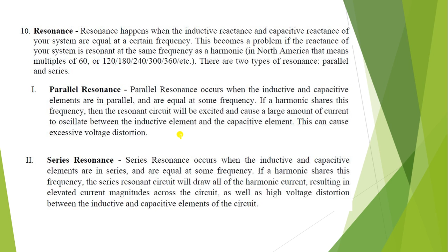Parallel resonance occurs when the inductive and capacitive elements are in parallel and are equal at some frequency. If a harmonic shares this frequency, then the resonant circuit will be excited and cause a large amount of current to oscillate between the inductive element and the capacitive element. This can cause excessive voltage distortion. Series resonance occurs when the inductive and capacitive elements are in series and are equal at some frequency. If a harmonic shares this frequency, the series resonance will draw a large amount of harmonic current, resulting in elevated current magnitude across the circuit, as well as high voltage distortion between the inductive and capacitive elements of the circuit.